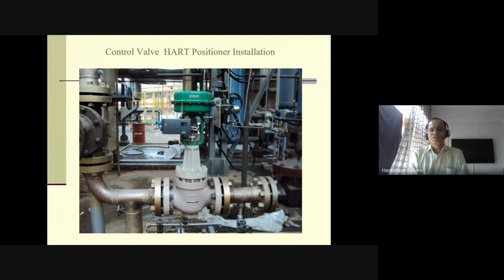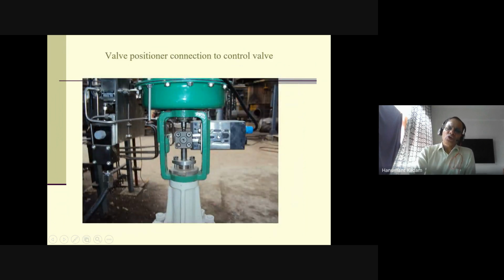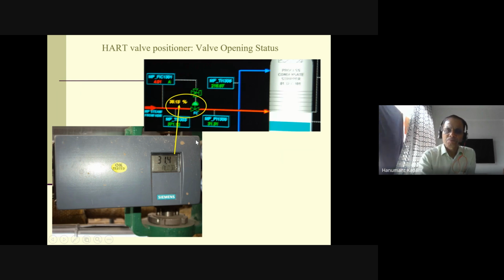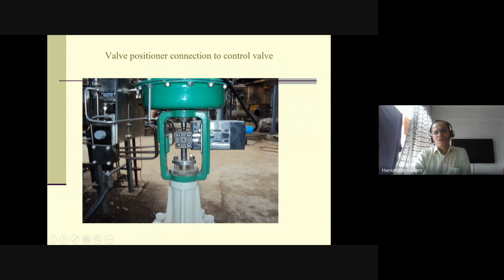If you see the valves actually installed in the industries, you see this pipeline, then isolation valves, and this valve you can see is a high pressure, high temperature valve. You can see the positioner here. This is the HART positioner, and you can see the linkage to the stem here. It is slightly visible, or you can see the back side or rear side of this. This is the stem, where you can see the link to the positioner mechanism here. So we are going to discuss this now.